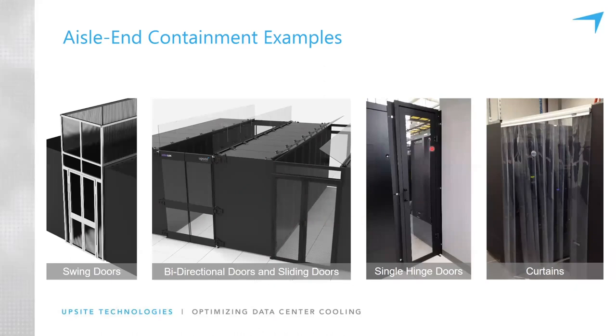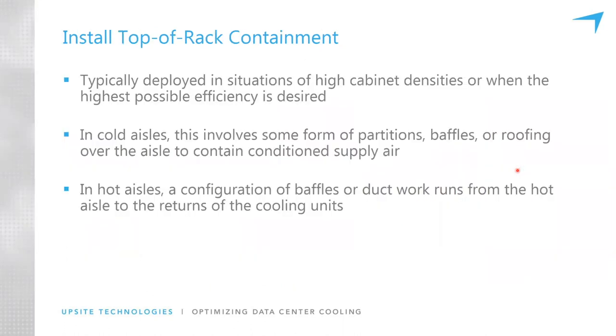This is a single swing or a hinge door, and this door just swings, has one motion out, and is hinged on one side for a very tight application, such as against a wall or a column and a narrow aisle of, in this case, just 2 feet. And then of course, curtains, which we're all familiar with. These can be a way to solve some very challenging problems. They're a less expensive solution to some of the more rigid containment, but they do have their downsides, and they can improve conditions as well. So a number of different ways to address airflow management at the end of the aisle.